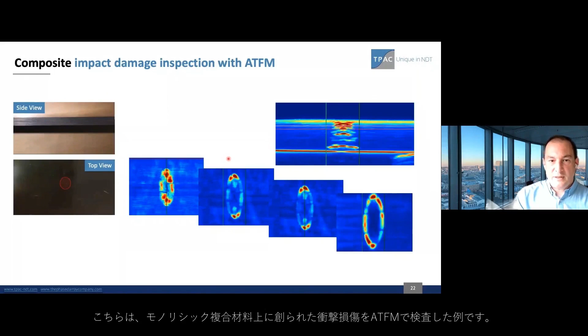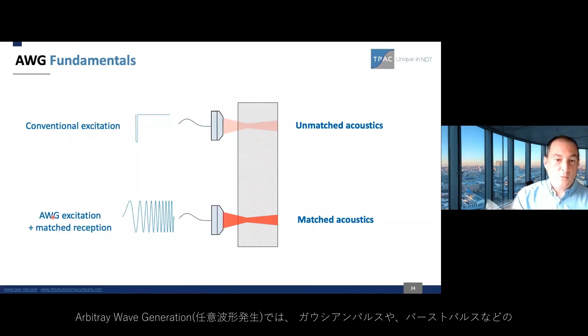Arbitrary wave generation is another technology, quite interesting. In normal ultrasound, we normally excite the probe with a negative square pulse. In this case we can speak about unmatched acoustics. In arbitrary wave generation, we can excite the probe using different wave shapes, like Gaussian shapes or chirp or burst. On top of this, we can receive the signals using a matched filter, and this matched filter is like a demodulation of the emitted signal. So in this case, we can talk about matched acoustics.